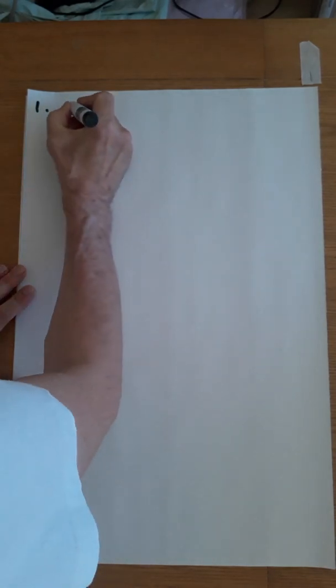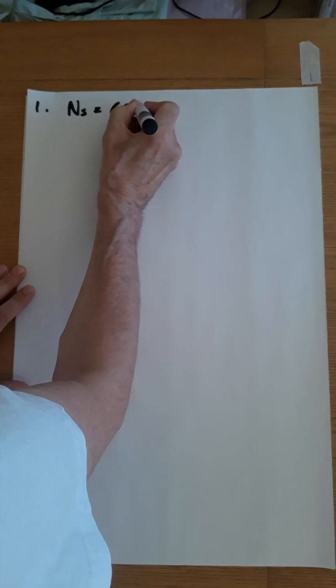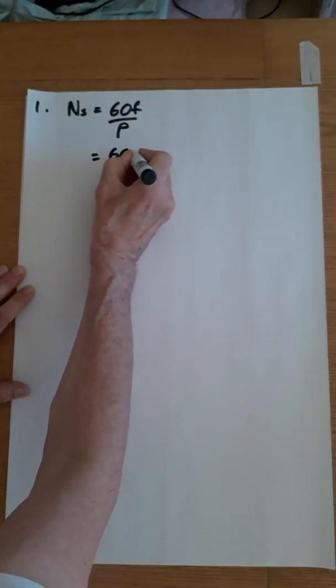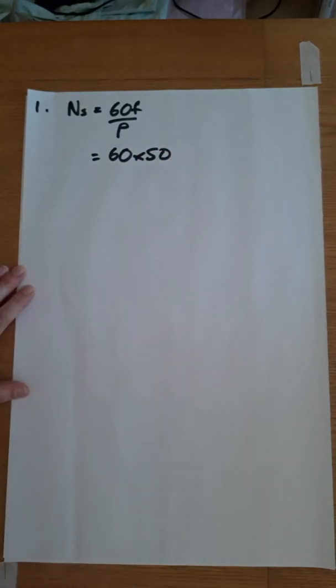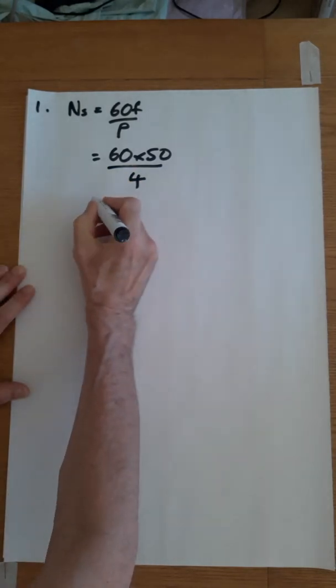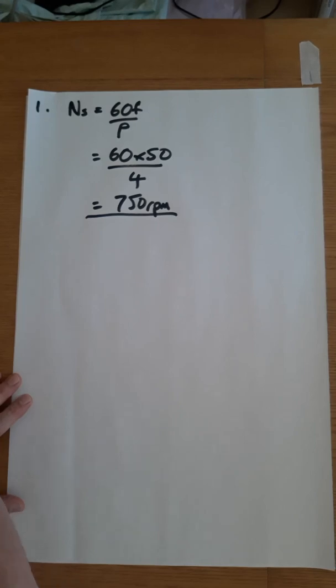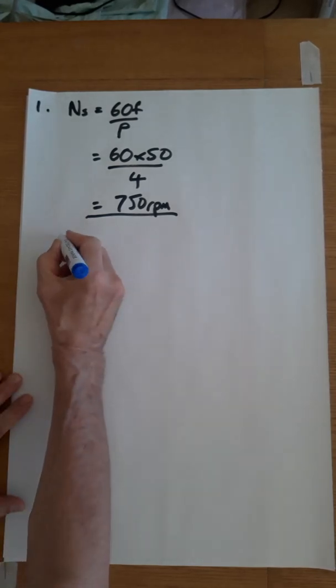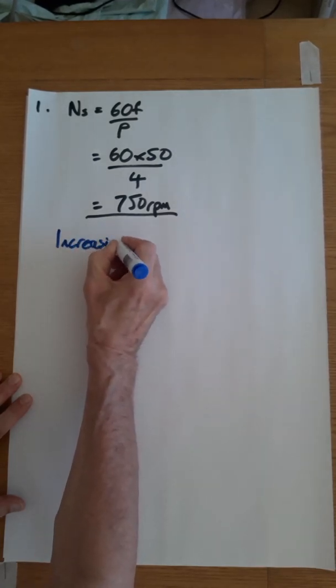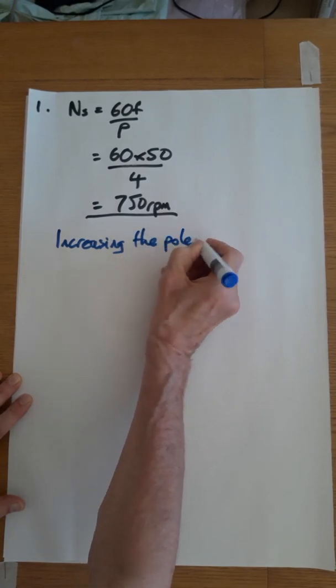Question one states: you have an eight pole induction motor on a 50 hertz supply — what is the synchronous speed in rpm and what has been the effect of increasing the number of poles? Formula: ns = 60f over p. Put the numbers in: 60 times 50, eight poles is four pairs, giving you 750 rpm. Increasing the number of poles reduces speed.